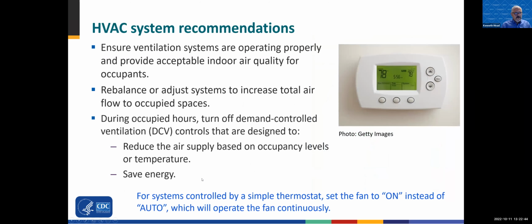More HVAC recommendations: ensure that your systems are operating properly and provide acceptable indoor air quality for occupants. Rebalance or adjust systems to increase total airflow to the occupied spaces. This is especially important during occupancy. If you have a variable air volume system or an occupancy-triggered HVAC system, you want to make sure that it's not shutting down the airflow when periods of occupancy are occurring or when there may be contaminant generation. For simple systems, that's as easy as taking your thermostat and putting the fan in the on mode so that airflow continues to pass by that filter and get cleaned.